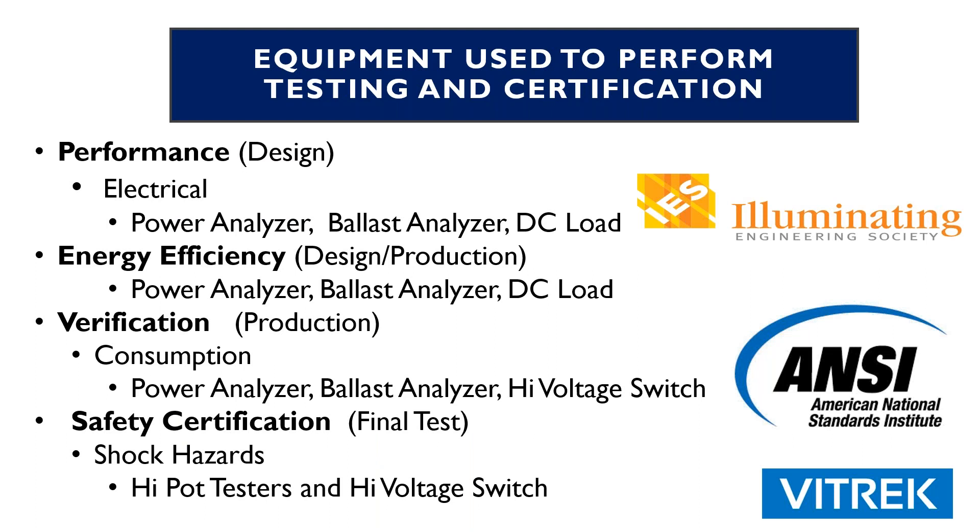Now we're going to talk about what type of equipment you need to be able to perform these tests. From the performance standpoint, usually on the design side, for the electrical parameters you can use a power analyzer, a ballast analyzer — which is a product that Xitron, a company that Vitrek bought a few years back, made for the fluorescent market — and certainly a DC load, which we're going to talk about in a little bit.